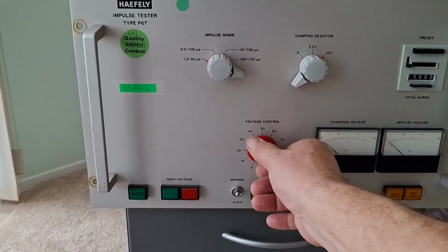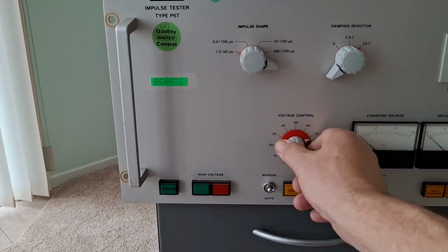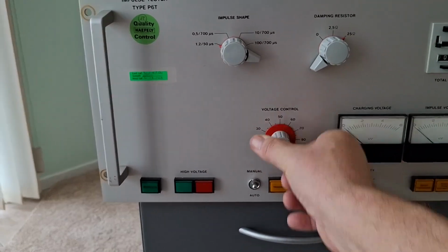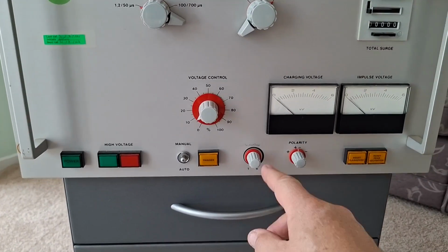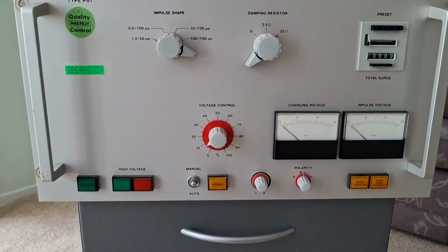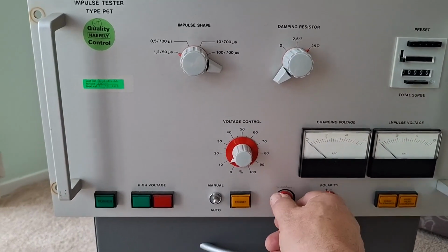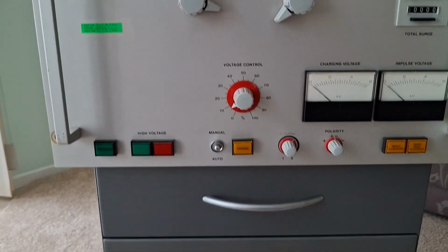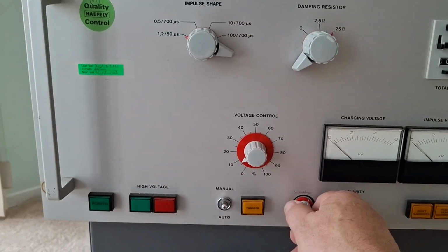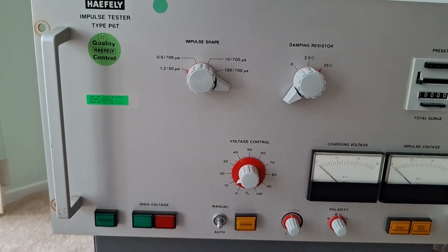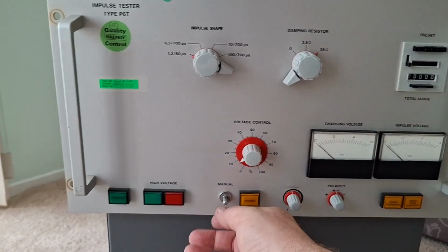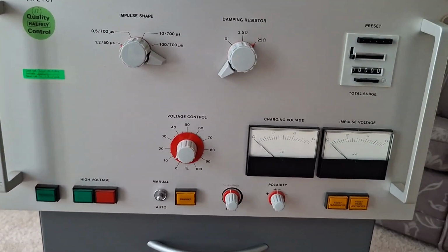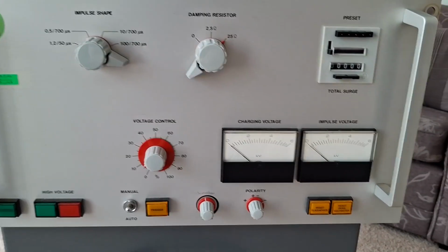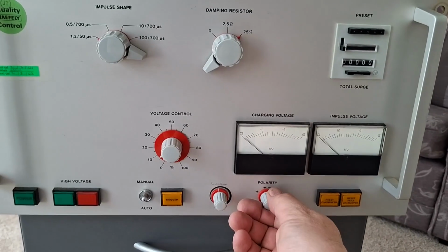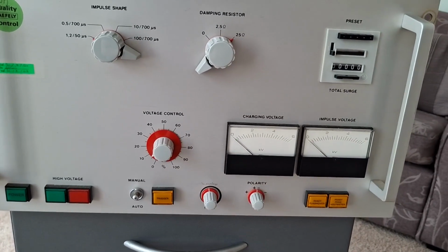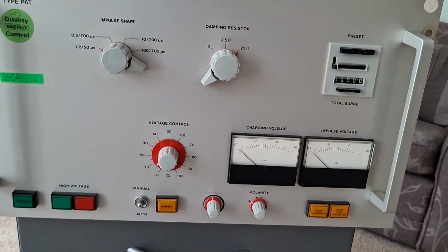There's a voltage control here which goes from 0 to 100, and 100% in this case would be 6 kilovolts. There is surges per minute, so it would appear to me that you can set this up to do, say, anything between 1 and 6 surges per minute. Set it on auto and it'll just keep sending out pulses until you switch it back to manual. And there's a polarity switch here, so there's an opportunity to switch to a negative pulse, a positive negative pulse, or a positive only pulse.